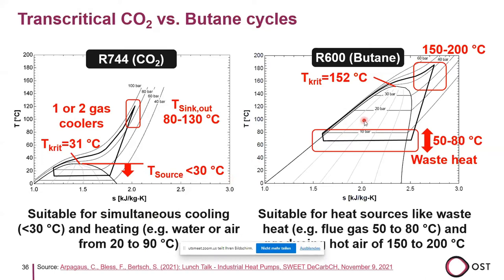On the right here, we have butane as an example in the transcritical cycle. And then you see that the source temperature can be very flexible. So waste heat from industry could be used here as a source, and then temperatures of 150 to 200 degrees are reached with butane. So it could be a useful fluid for such kind of temperature conditions. And there are other fluids for transcritical which could be useful.